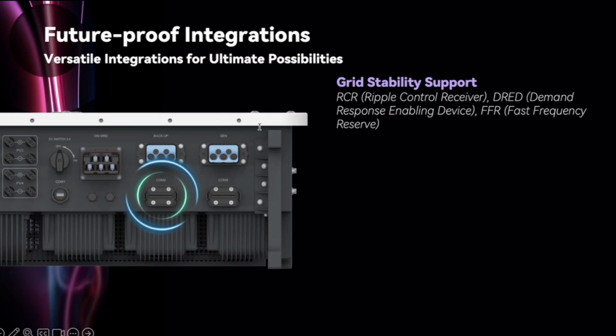To manage this, the grid operators introduced remote control mechanisms, and that is where RCR and DRED come in. They allow the grid operator to remotely limit or control the inverter's power output or input when the grid is under stress, for example, by reducing the export power, pausing the generation, or adjusting the demand. Even though South Africa doesn't currently have such requirements, as the penetration of distributed energy grows, similar standards might be introduced in the future. That is why it is important to be prepared. The good news is that thanks to our strong R&D base, our system already supports these functions, meaning that we are future ready for smart grid integration and compliance.